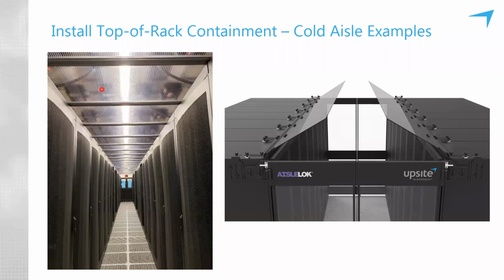So from a fire suppression standpoint, this works well in most all environments and is supported with your local jurisdiction, because these panels or the inserts will flutter out of the frames before the sprinkler system goes off. And we're talking like way less than a pound each. These are like leaves falling off the tree in the fall.